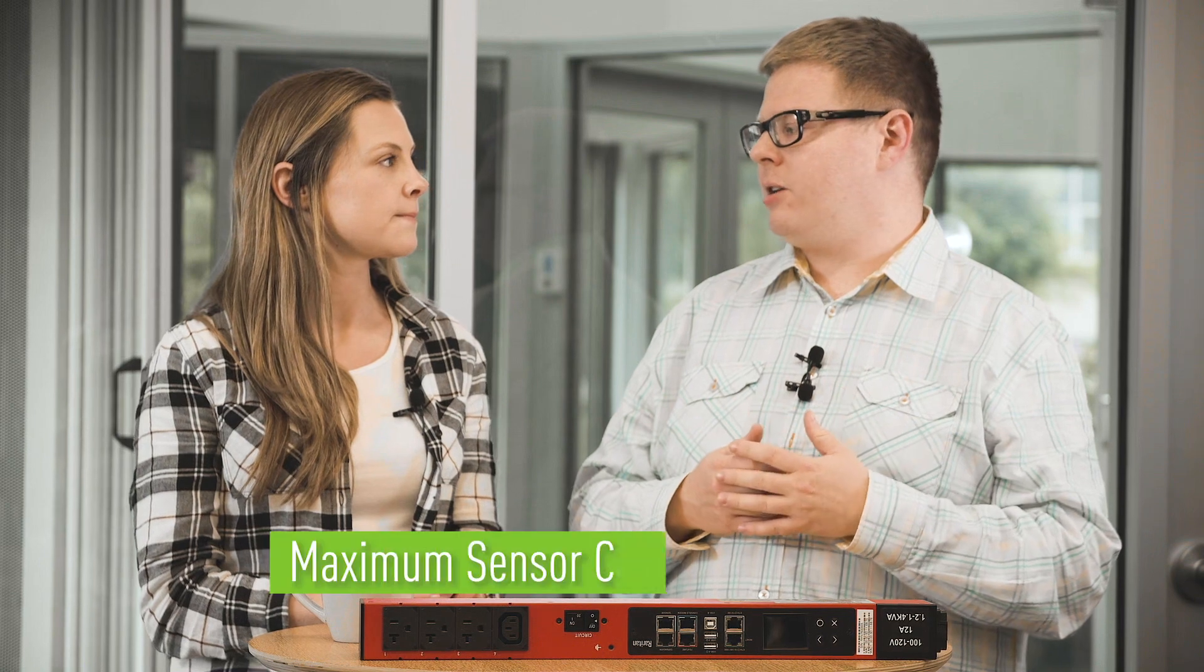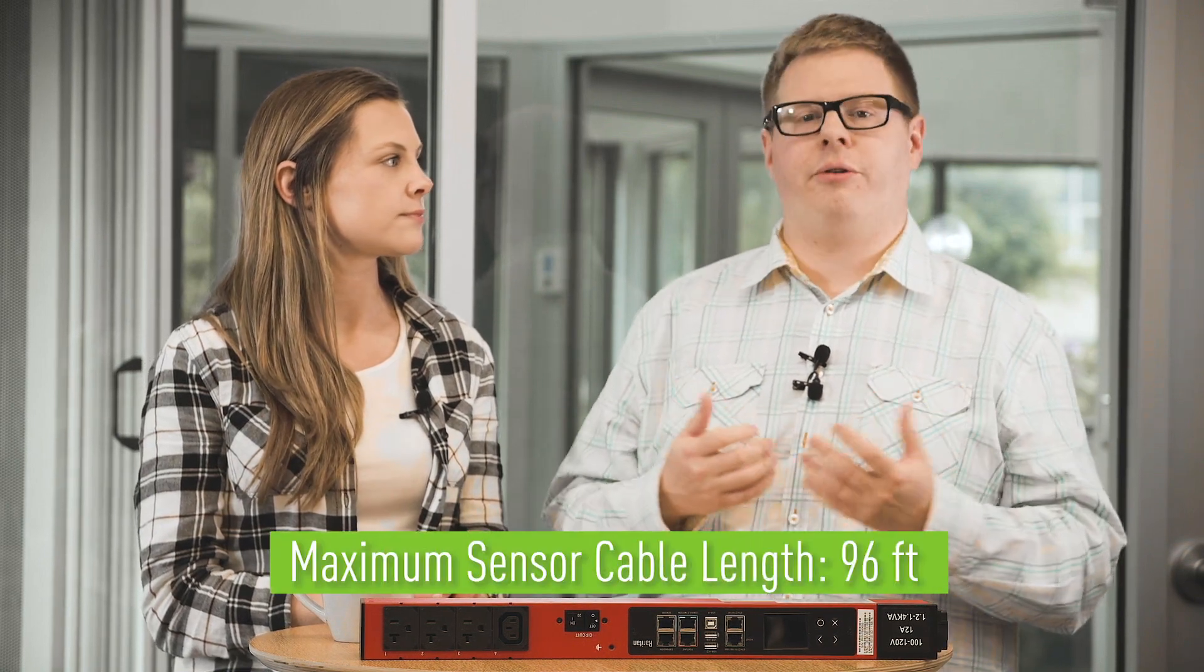So, what are some limitations that a user might face with smart sensors? You know, that's a good question. Most typically, we get the question about distance. The amount of length between the IX7 controller and the sensor port, and then the last sensor in the chain and how far they can run that. The approximate length limitation is around 96 feet or 30 meters.